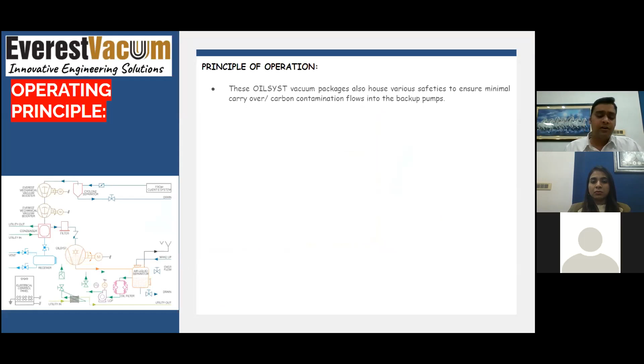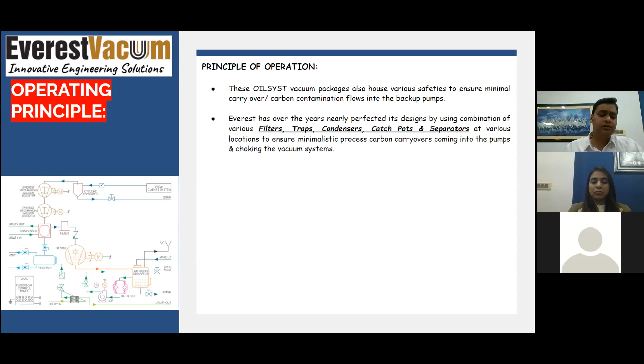Taking you to the operating principle of the vacuum system, we offer it with various safety interlocks. We have control on carbon carryover and vapor carryover into the process or the vacuum pumps. With this, we offer various filter traps, condensers, catch pots, and separators, as explained. We have various safety provisions and interlocks in the systems, leading to better efficiency of the vacuum pumps in the process.